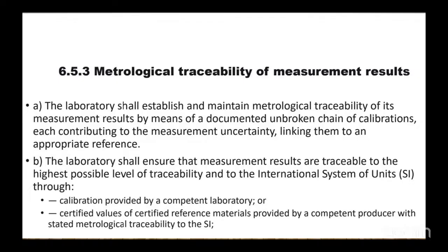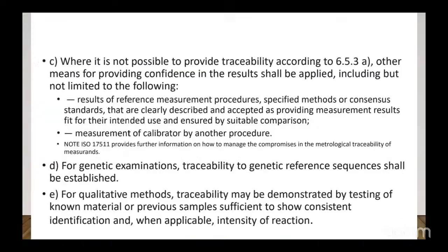So two things you can do: you can take the equipment to a calibration lab. Like in Nigeria, we have a calibration and metrological traceability lab. If you can't do that, you could call for experts, people who have a license for that. They could help you do those calibrations and document it. And they also have to show proof that those things have been done and the equipment passed calibration. Am I communicating?